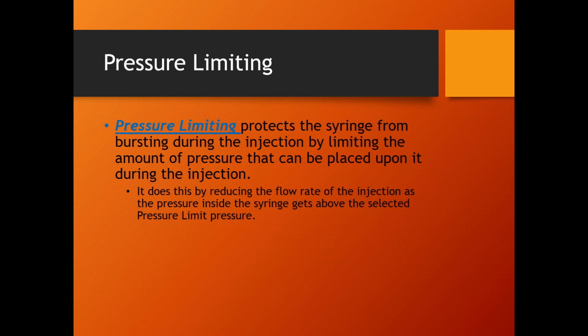But to be honest, hitting the pressure limit is a very rare thing. More times than not, it's some sort of, I don't want to say operator error, but that's the best way to describe it. It's some sort of error that the technicians or the doctors or nurses have made during the actual injection that caused the pressure limit. I mean, if the protocols are set up the way they're supposed to be set up and we're using the right size tubing and the right size needles and the right size catheters, it should shoot just fine. If there is a pressure limiting, something's gone wrong that is usually relatively simple to correct.